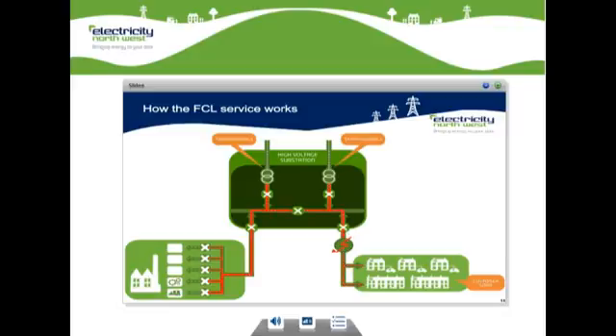All our protected devices see the fault current, but the closest one to the fault operates first and disconnects the customers on the network beyond the fault. Now, if the total current is less than the rating of the equipment, everything operates normally and safely. However, if the sum of all the currents running through that breaker is higher than its rating, then the equipment could be damaged and the fault could spread.